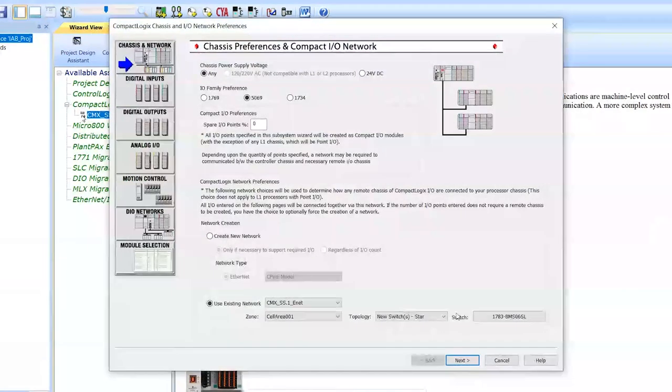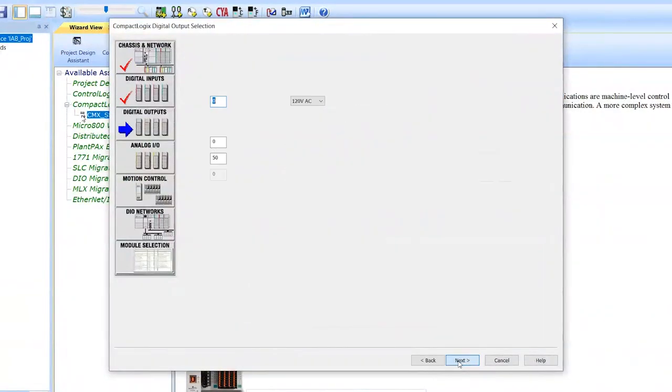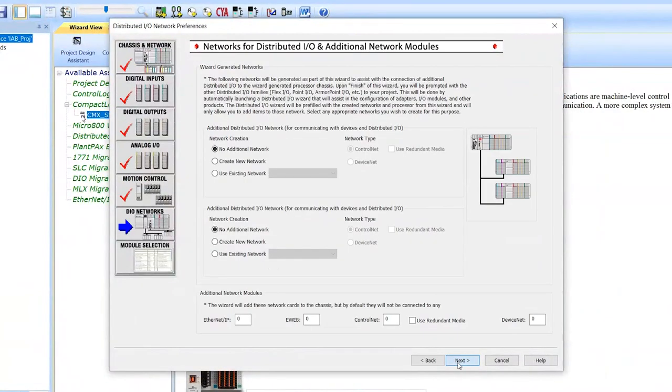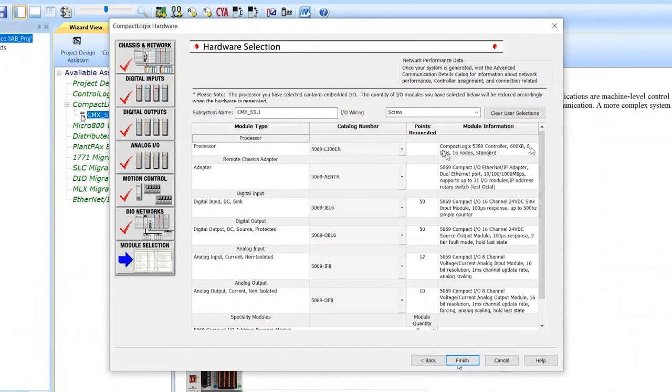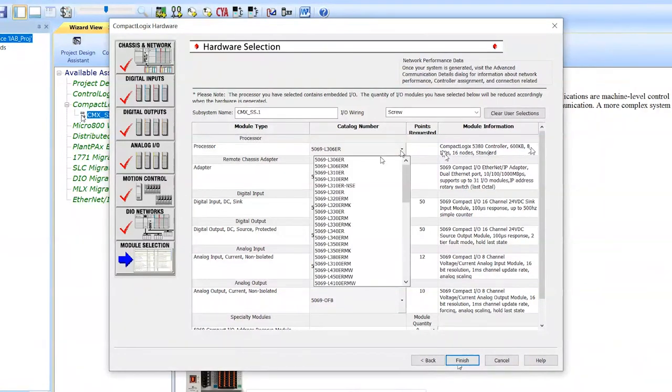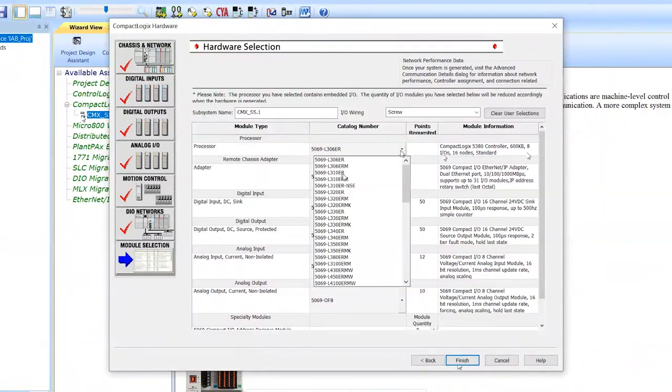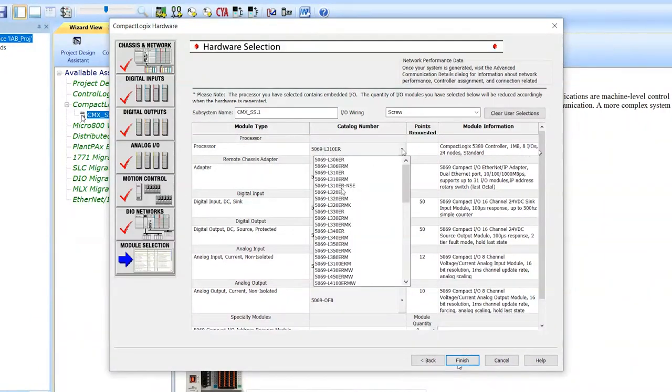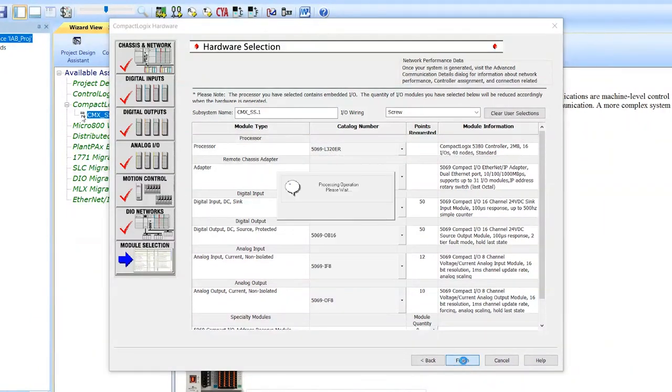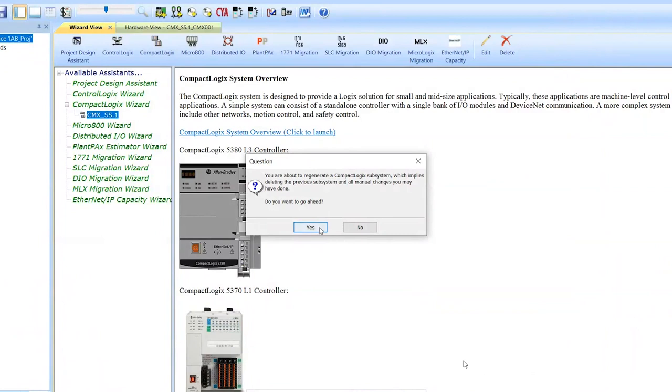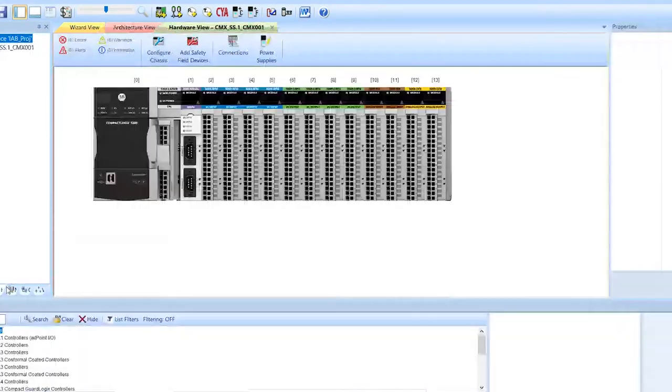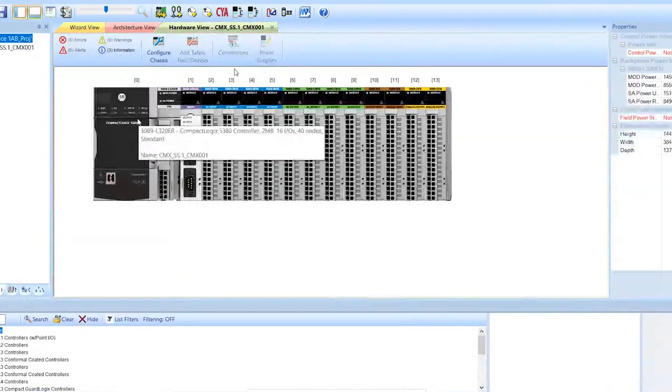I can go back in there. I can open up the wizard. I can scroll through to the end. And I can change that controller because if you look at this controller, it supports eight I/O modules. So if I go to a 310, this is also eight. Go to a 320, that's 16. So now when I finish and I look at the rack, it's put everything in one because this processor supports that many.